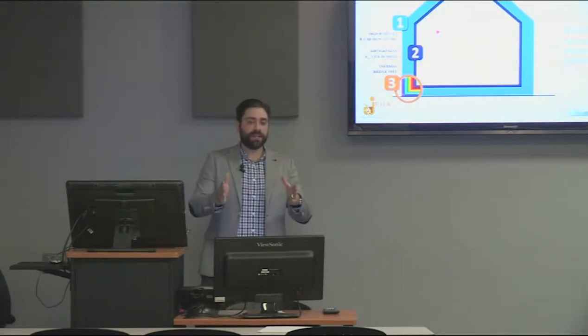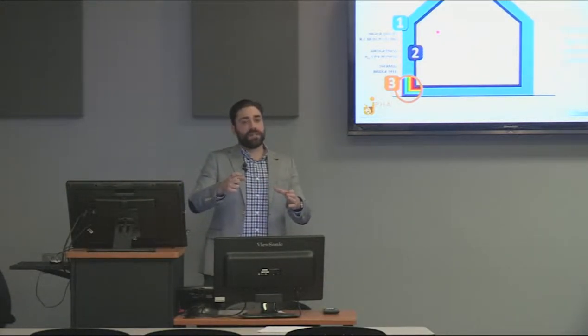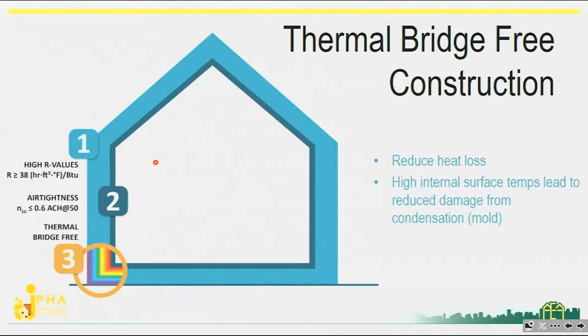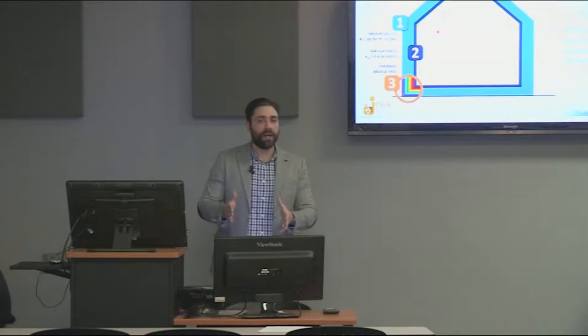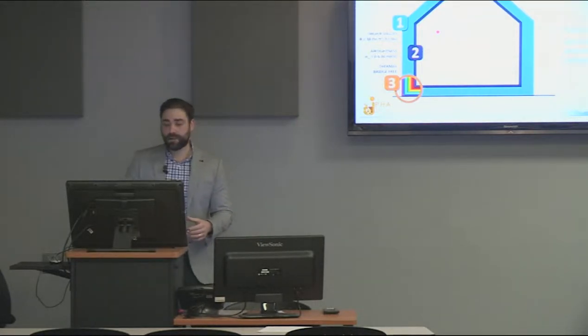Typically what ends up happening is as you're losing heat through those assemblies, that section of the wall gets cold or warm. We're really worried about this in the wintertime when you have an actual cold stud connected to the drywall. If the temperature of that surface drops below the dew point, you can have condensation taking place on that wall. So from a durability standpoint, we need to look at and address every thermal bridge in the building.